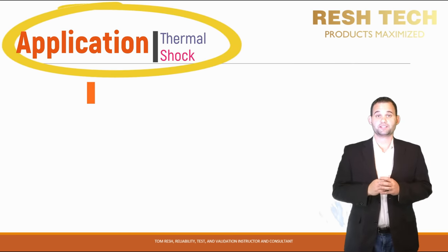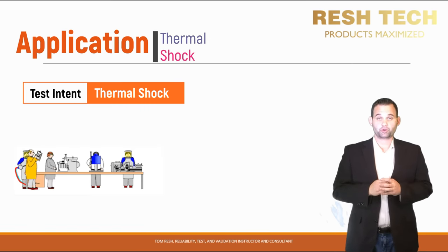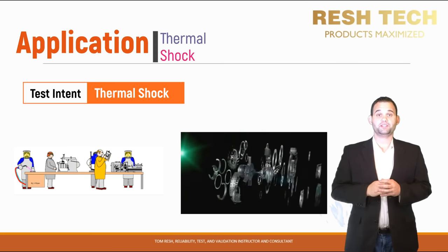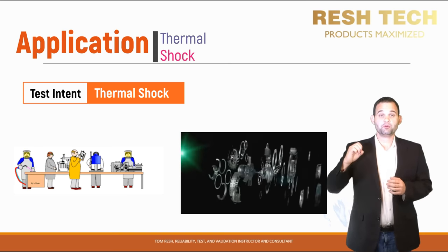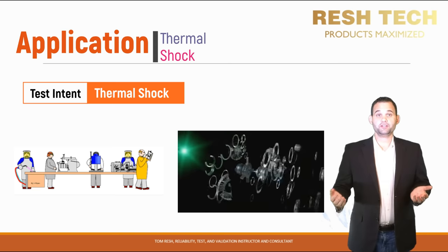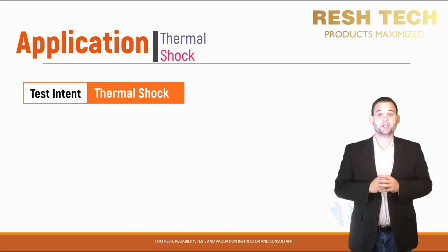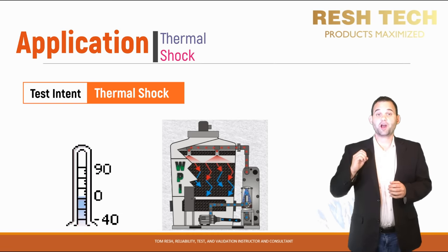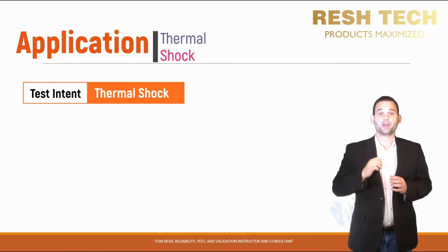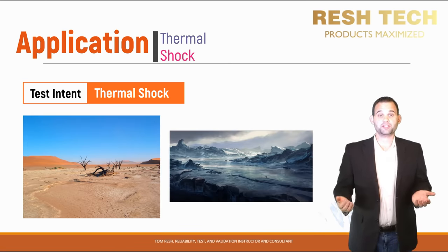Let's jump into thermal shock application and setting up a thermal shock test. First, let's cover the intention of the test. Is this a manufacturing screening process or a design verification or validation test? For production screening, you will need to determine the temperature range and number of cycles required to detect latent defects while ensuring that stress levels and cycles do not produce unnecessary damage or fatigue. For design verification and validation tests, you should look at both temperature and cyclical data for how your system heats and cools internally from its own operation and the worst-case environmental temperatures.